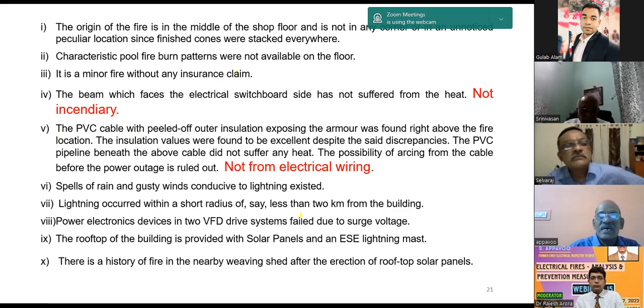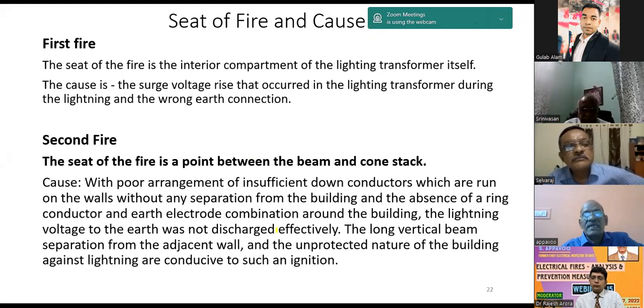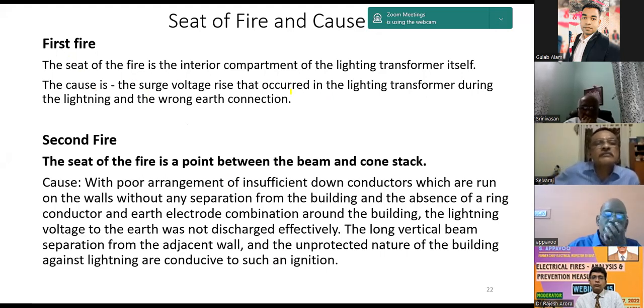Lightning occurred within a short radius of 1 kilometer. Power electronic devices were faulty, and there was a rooftop with solar panels and ESE lightning protection. The history of the fire also confirmed that a similar fire occurred 2 months earlier under the same condition. So a strong doubt arises whether the fire can be due to lightning. So there's no doubt the first fire is due to the surge voltage rise.